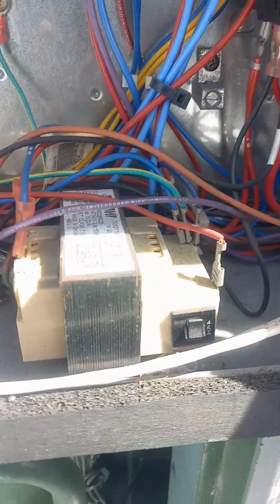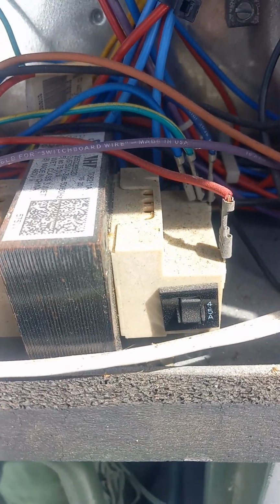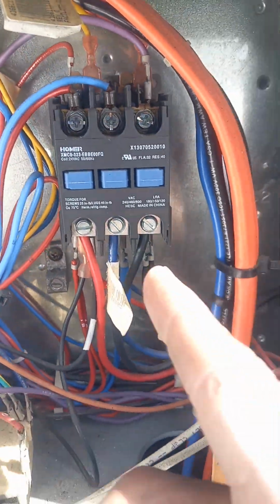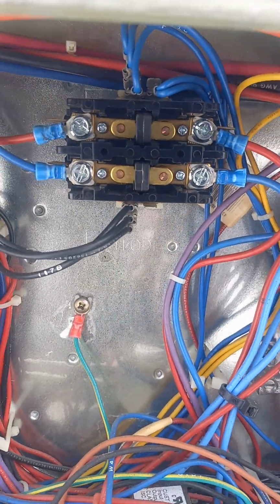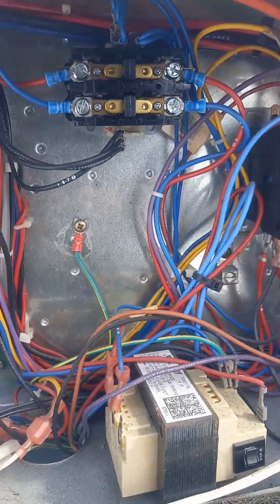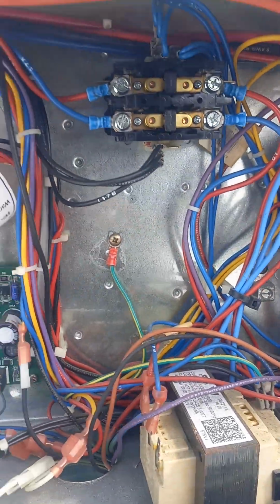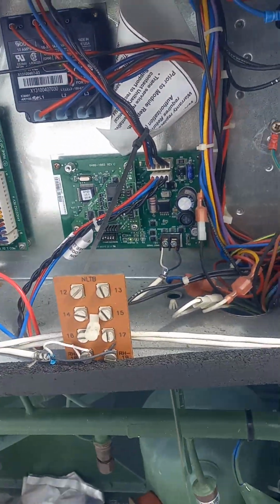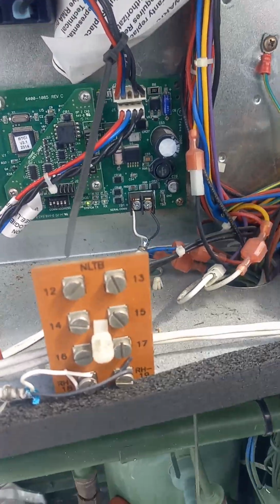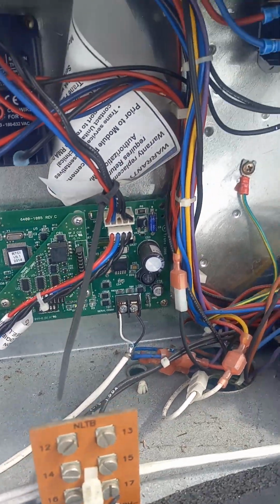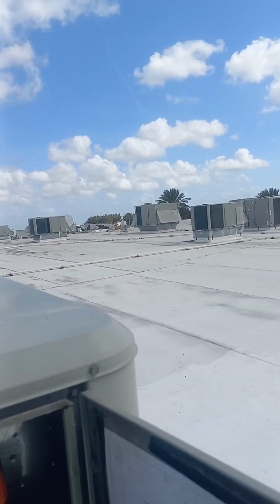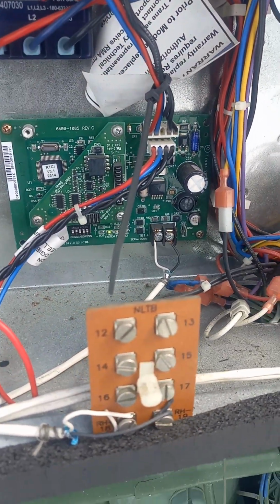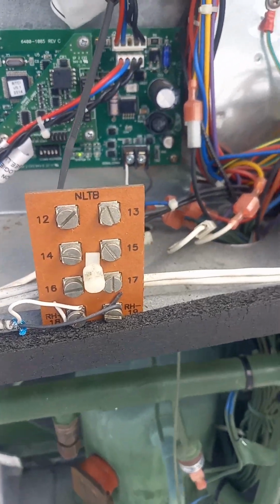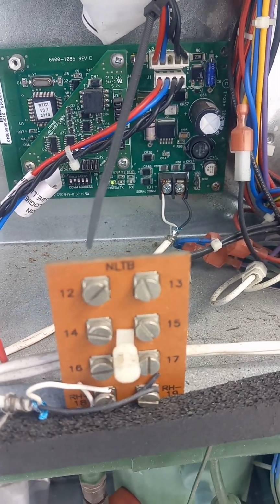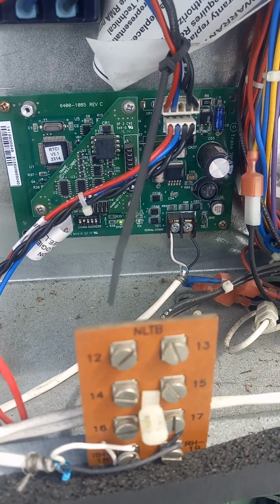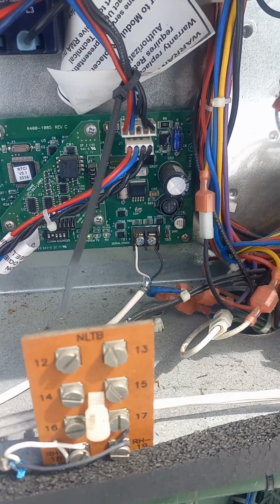So this is a transformer that's converting high voltage to low voltage to give 24 volts to control this contactor, which is the compressor contactor, and that contactor right there is a blower contactor. And all of those, you have to have low voltage to actually operate them. And this board actually has a communication board from Trane. This communication board just has these wires right here, which are daisy chained between each one of these units on the roof, and then each board has its own address. So when it's daisy chained to each unit, it's going back downstairs to the supervisory controller, where you can log into the computer and see each unit. Each unit has to have its own address.